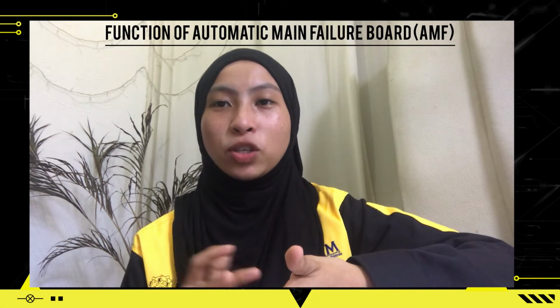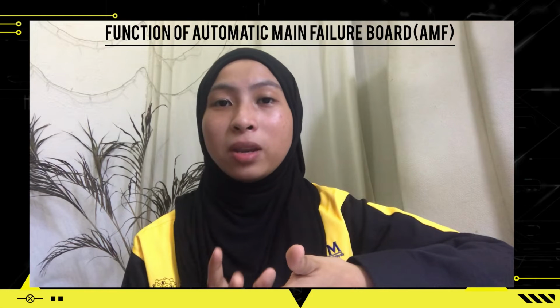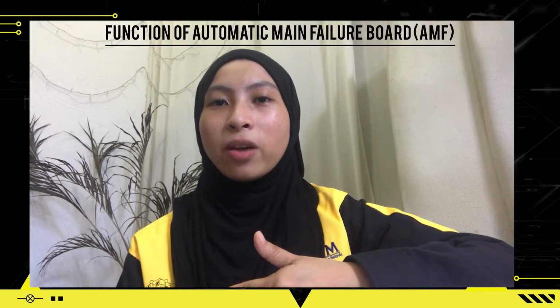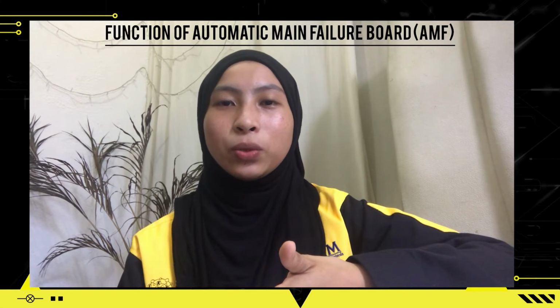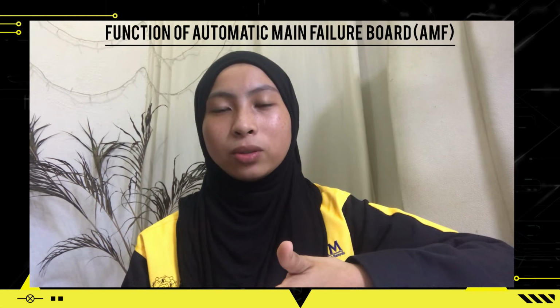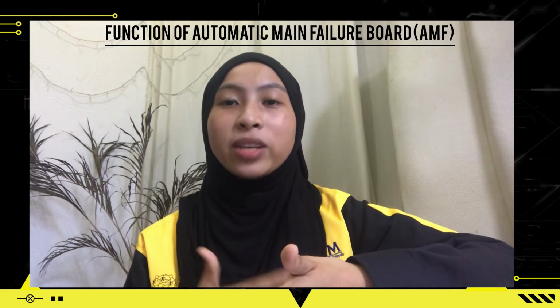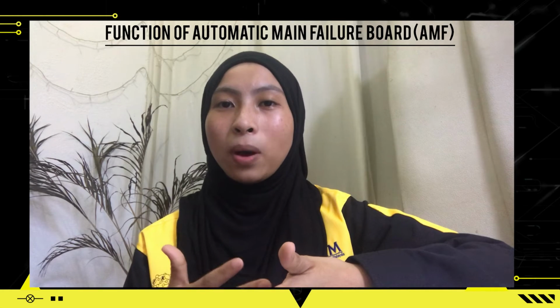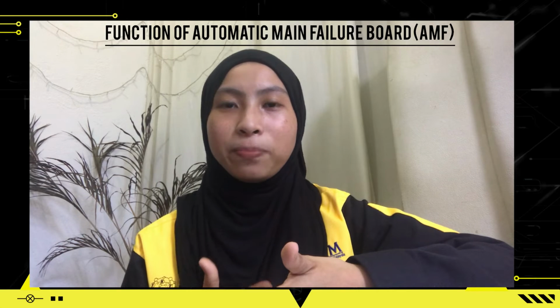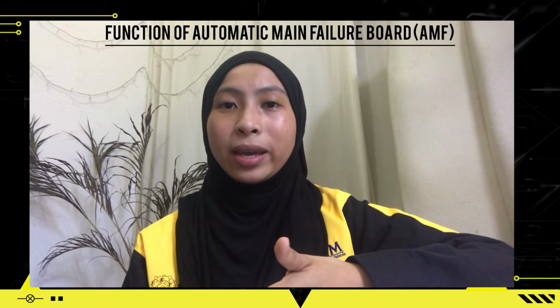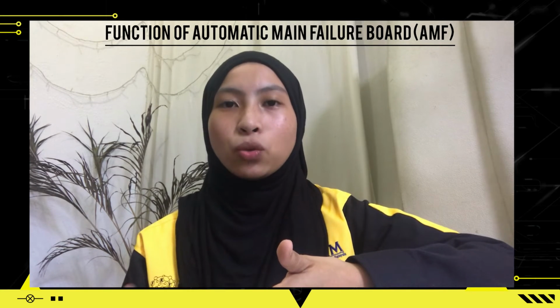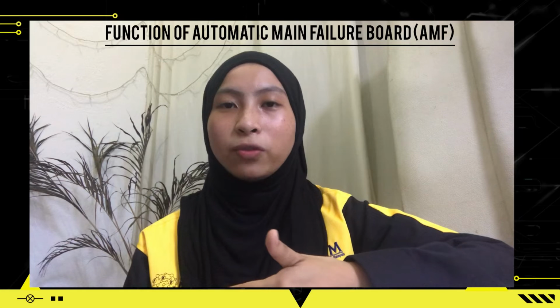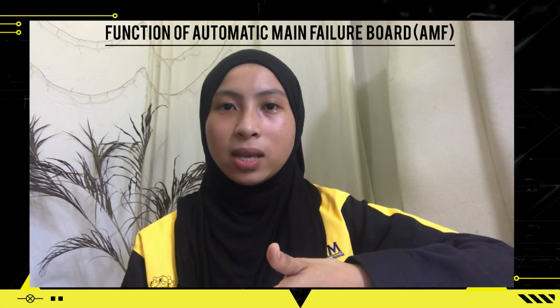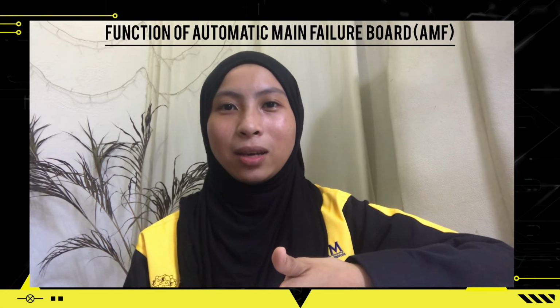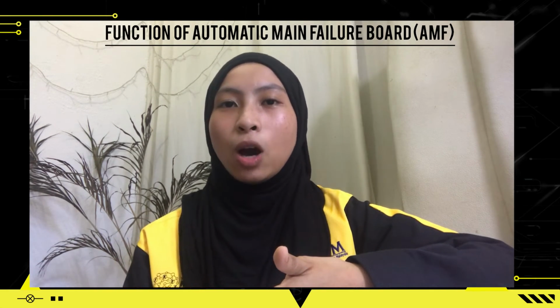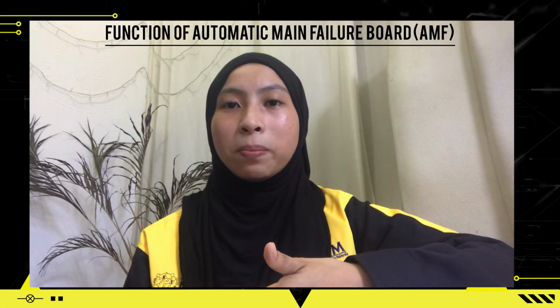And the last one is question 4. Briefly explain the function of automatic mains failure board, which is AMF. So AMF is automatic mains failure panels, often referred to as automatic transfer switch (ATS) panels. They make the power switch to emergency standby generators in the event of a significant loss of main power or total blackout. Without AMF panels, generators need to be operated manually, and that can mean lost data, potential damage to electrical equipment, and also a huge amount of disruption. AMF also monitors the incoming AC main supply, activates the standby generator when mains power fails, and makes an automatic electrical transfer of the building's load from the mains to the generating set.